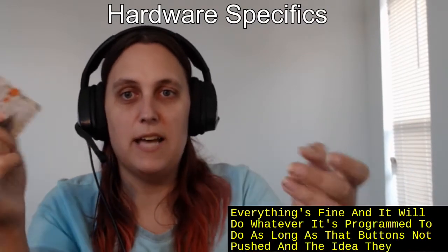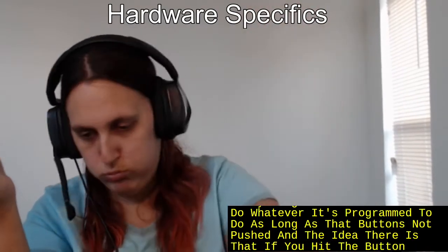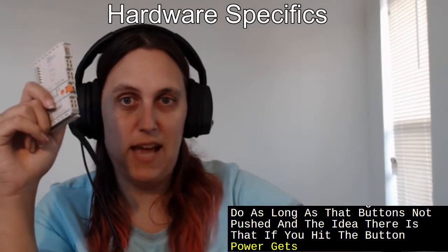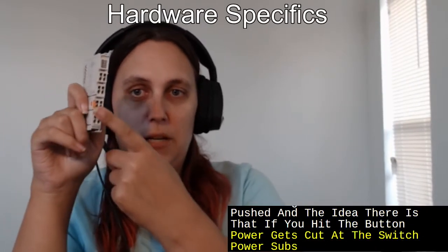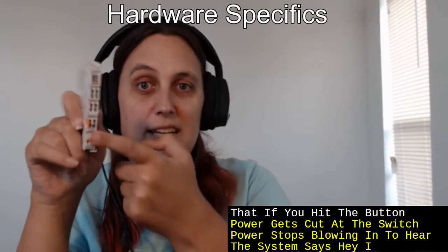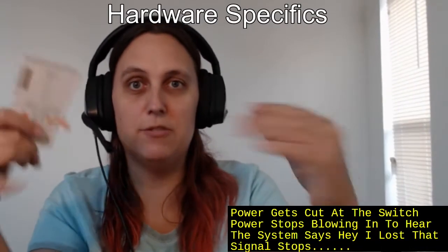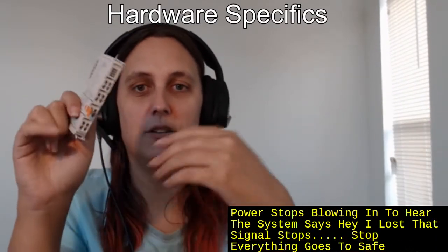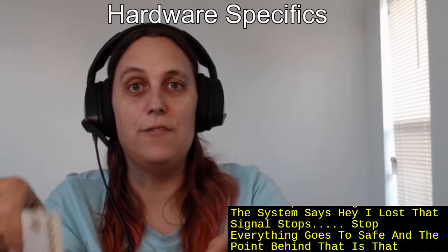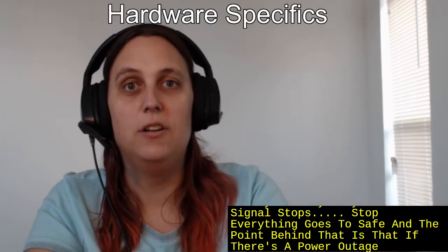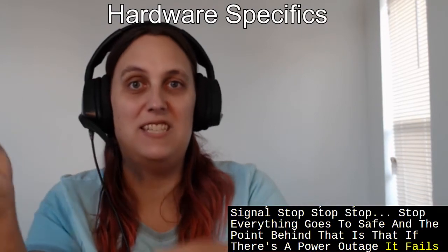And the idea there is that if you hit the button, power gets cut at the switch. Power stops flowing into here. The system says, hey, I lost that signal. Stop, stop, stop, stop, stop, stop, stop. Everything goes to safe. And the point behind that is that if there's a power outage, it fails to safe.